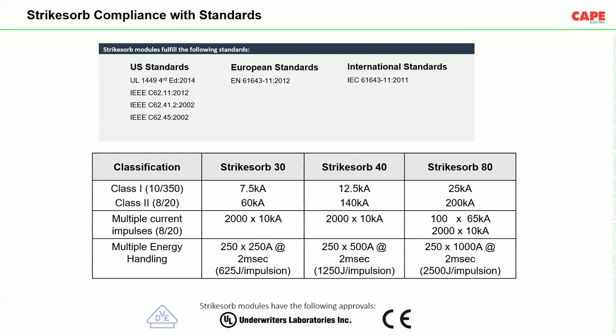Now for these SPDs, the Strikesorb 30, 40, 80, the number of strikes, 2000 into 10 kiloampere, is made over a period of time. But for multiple strikes, one after the other, each of these SPDs is also tested 7 to 8 times continuously, that means immediately one after the other. So this is actually a very big advantage of these SPDs. You must have seen in the earlier picture that it is made with an aluminium housing.